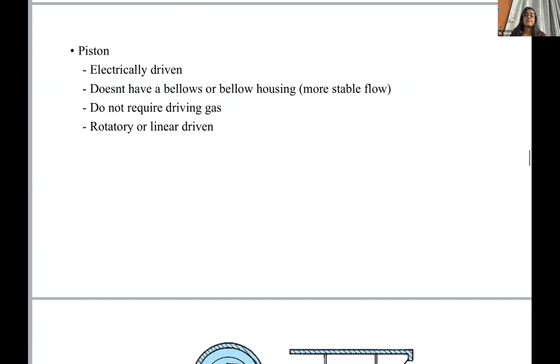The piston system is of two types, that is the rotatory and the linear driven system. As given in the A image, which is a rotatory system, the backward stroke of this piston system opens the first one-way valve, which pushes the respiratory gases into the assembly. The opposite stroke of the rotatory piston system opens the second one-way valve, via which the respiratory gases are pushed into the breathing circuit and delivered to the patient.